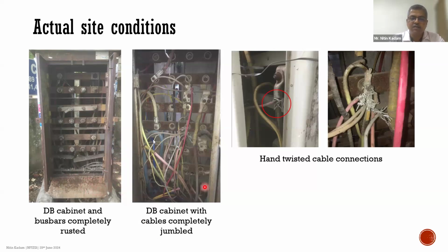Here there are completely haphazard wire and cable connections. Again, the bus bars are rusted. Here, a hand-twisted wire is connected. Again, hand-twisted wires are being connected. So this is the quality of wiring that is being done, and the power supply is coming to the building premises. And then we are trying to do the fault loop impedance test, which will not happen, it will fail. So it is high time that we are aware of all these requirements and we take care, talk to the stakeholders and the power supply companies, and get all these things corrected.